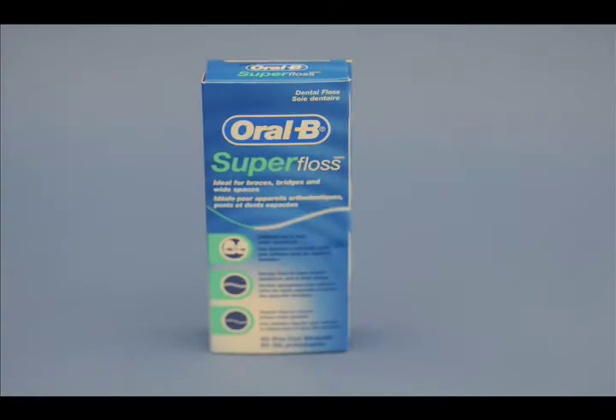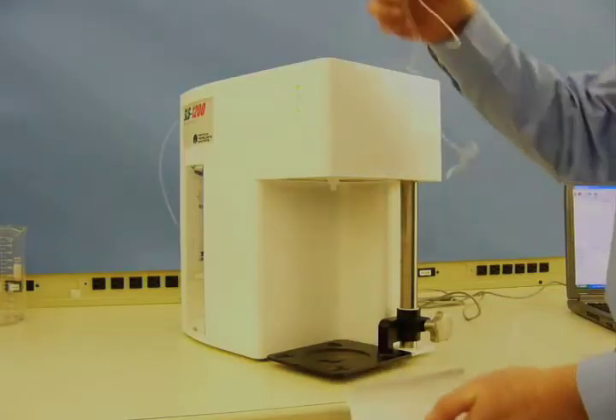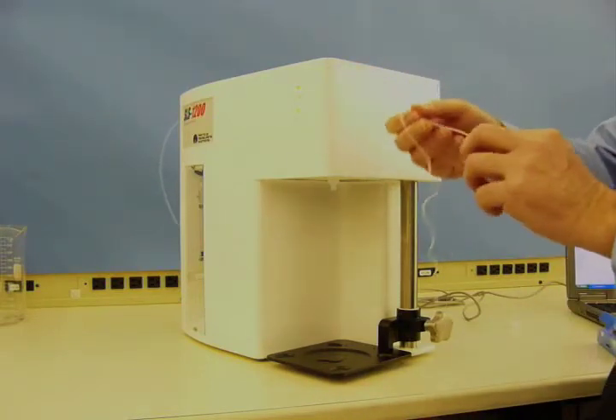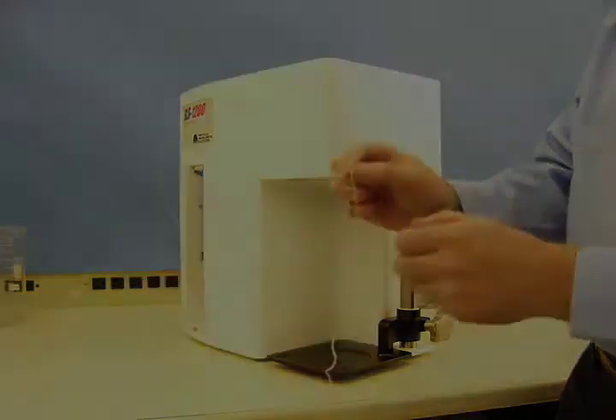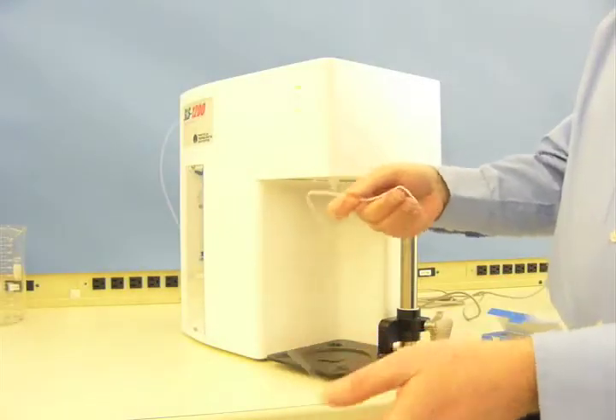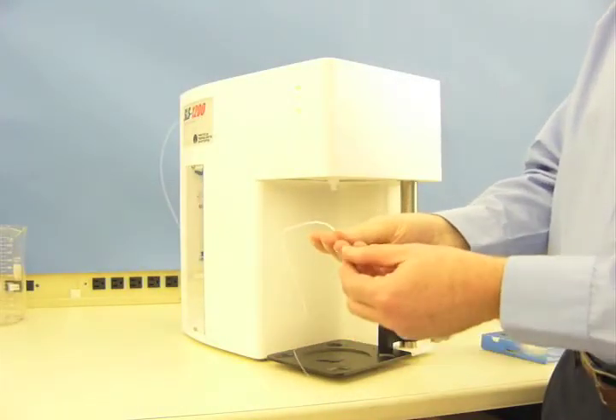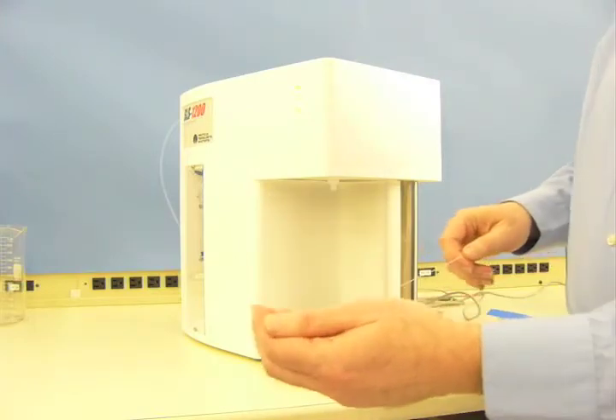Retrieve the box of super floss and extract a piece of floss. Notice that the shorter, skinny end of the floss is slightly bluish in color and appears to be coated in wax. This end should never pass through the capillary as the wax can be deposited on the cell walls, therefore adding steps to the cleaning process.